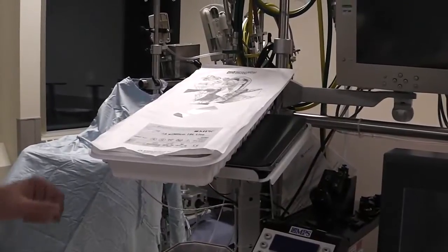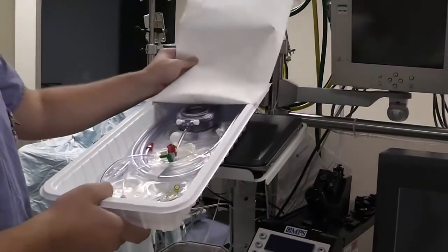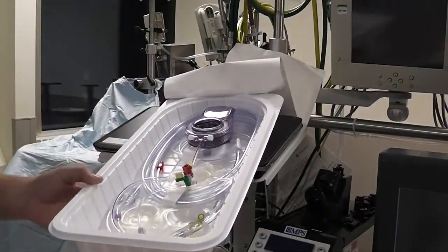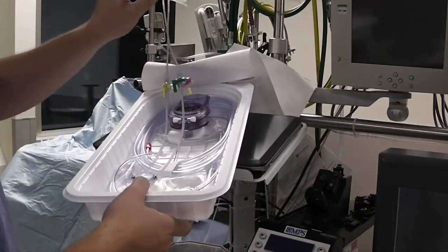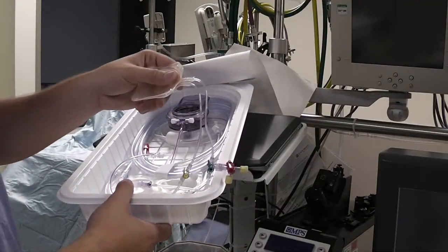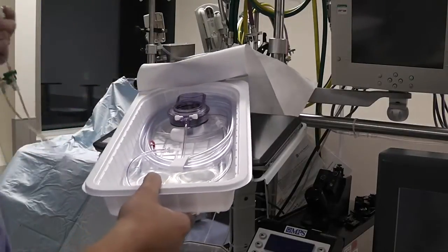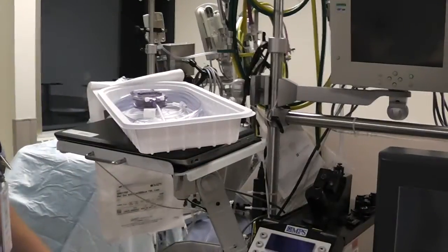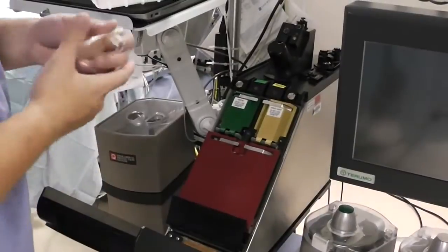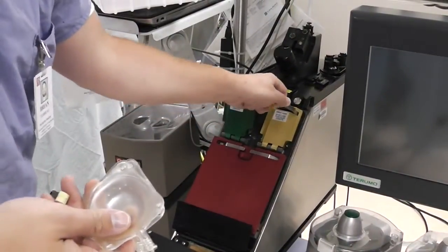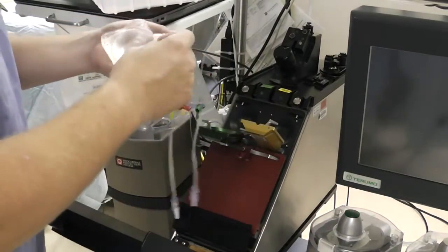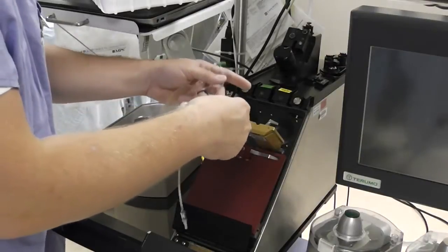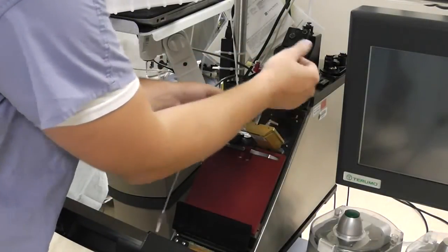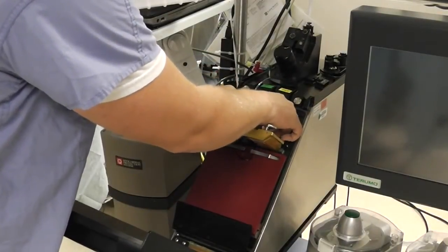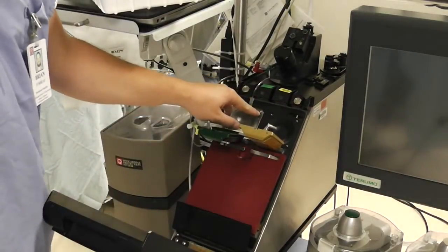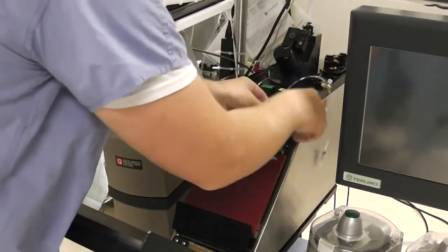Next, we're going to set up the cardioplegia. So this is the Quest system here, and the best way to get this set up is to remove these two small pouches here. One of them has a green stopcock on it, and the other one has a yellow stopcock on it. So we're going to take those out of the package, open up the Quest, open up the green and yellow side doors here, and then put the pouches into the corresponding section here. So the green one we're going to put into the green side. We're going to insert all 4 holes into the pegs, and the same with the yellow side.